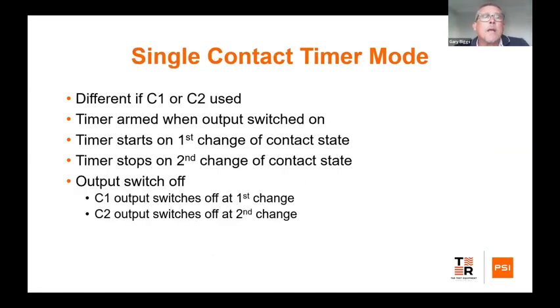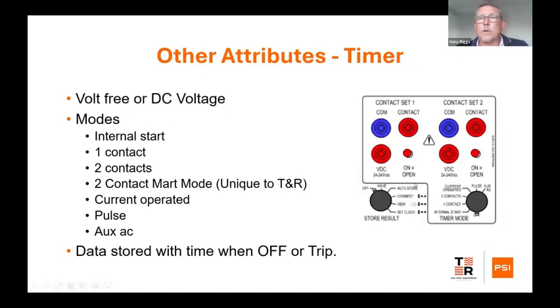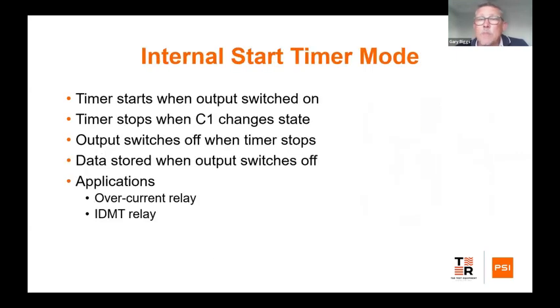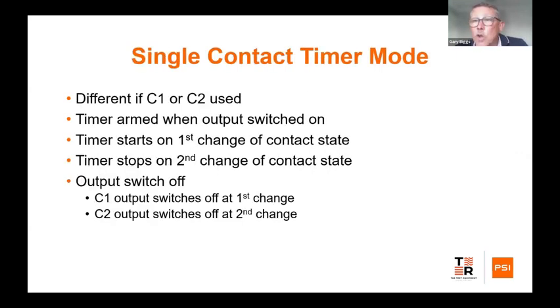single contact timer mode, and it's different if it's C1 or C2. If you look at the picture here, we have two contact sets. Most of the time when you're testing a relay, you're only going to be using one contact set, but some relays will have a start and stop contact set. So you can connect to those and we can test those with no issues. The timer is on when the output is switched on, and the timer will start on the first contact change, and then it will stop on the second change of contact. When it stops, it will store the time, and it will also turn the output off from the relay test set.